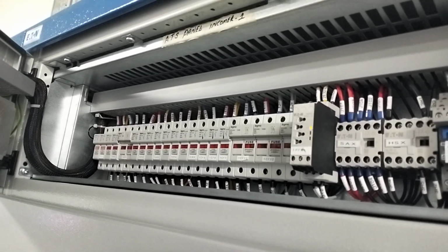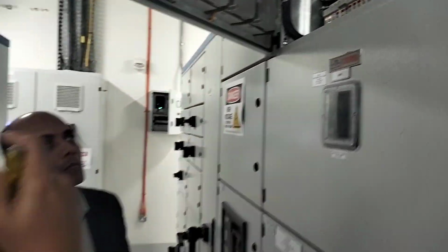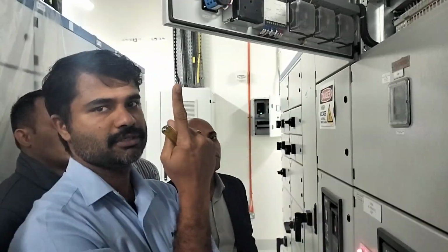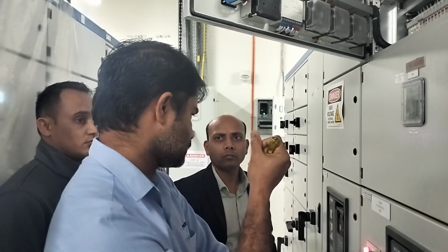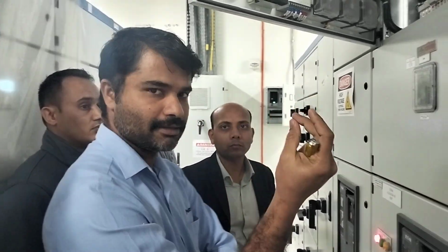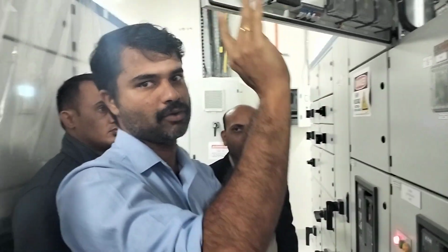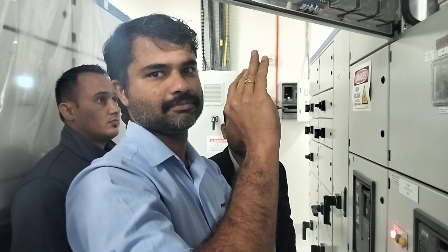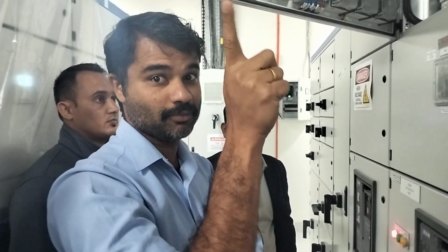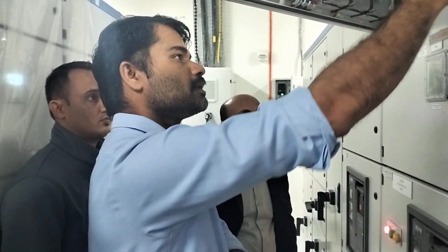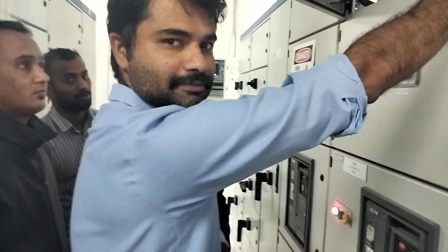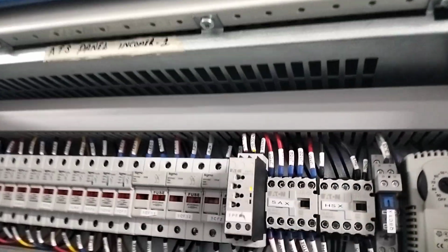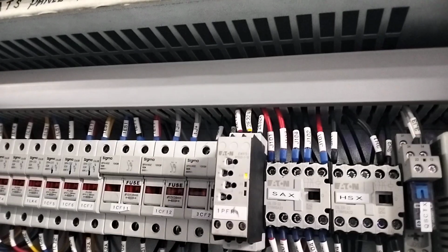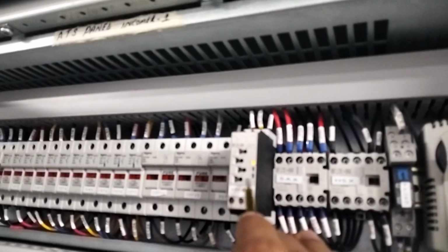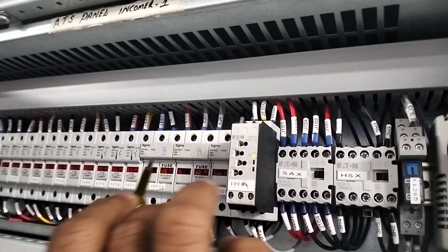And one more thing. Sometimes from the Karama there might be high fluctuation within a fraction of a second. The high voltage will come and go. At that time, everything will get disturbed immediately. One more thing, from experience, you have to come and look at this indication also. This is a healthy indication. If the indication is showing something empty, that means something is fused or blown, or there is no voltage.